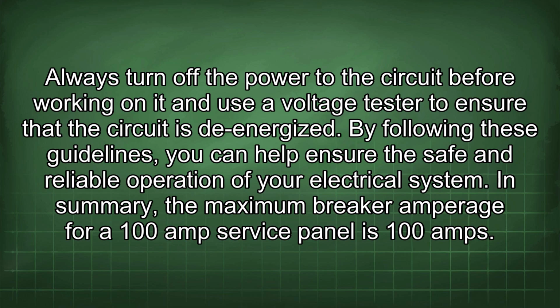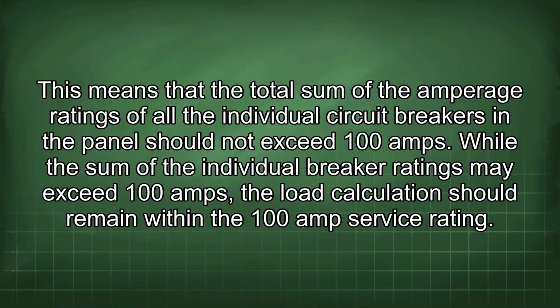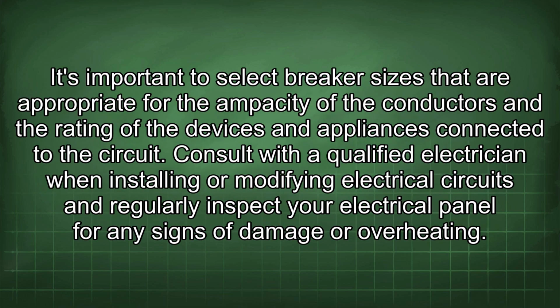In summary, the maximum breaker amperage for a 100 amp service panel is 100 amps. This means that the total sum of the amperage ratings of all the individual circuit breakers in a panel should not exceed 100 amps. While the sum of the individual breaker ratings may exceed 100 amps, the load calculation should remain within the 100 amp service rating. It's important to select breaker sizes that are appropriate for the ampacity of the conductors and the rating of the devices and appliances connected to the circuit. Consult with a qualified electrician when installing or modifying electrical circuits and regularly inspect your electrical panel for any signs of damage or overheating.